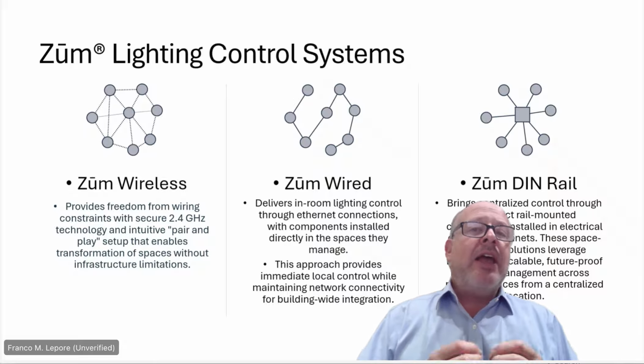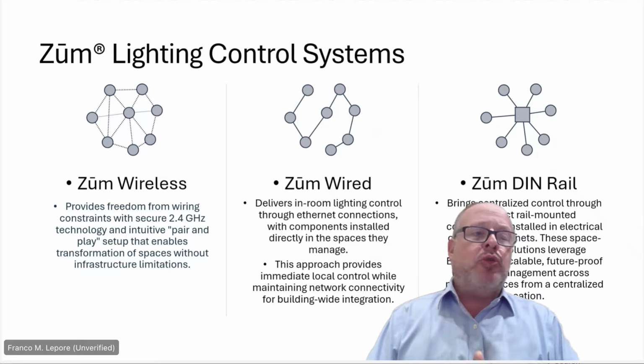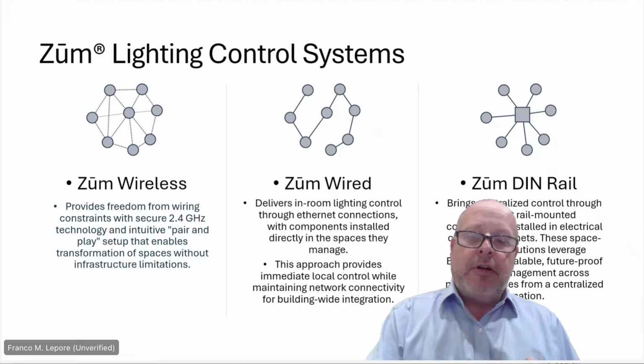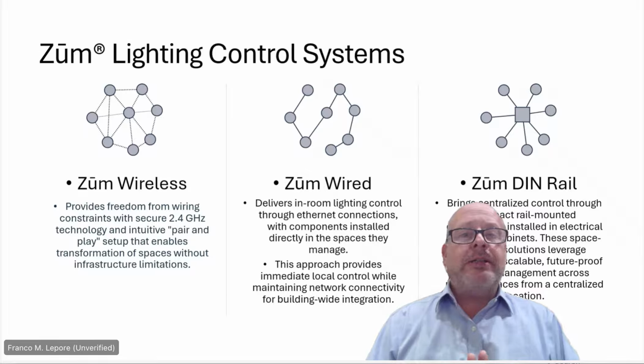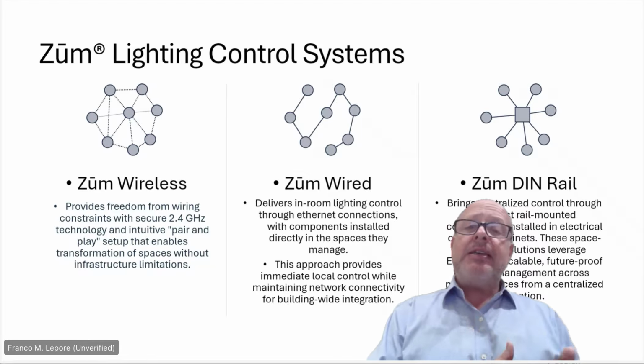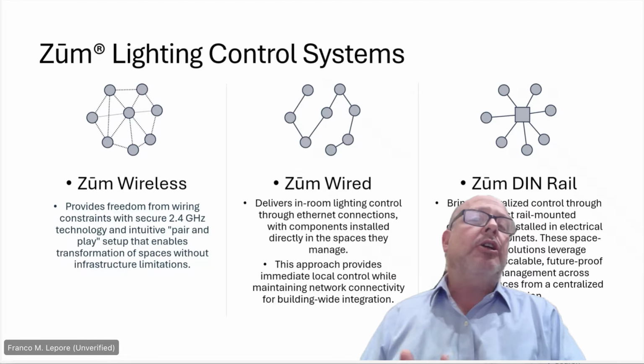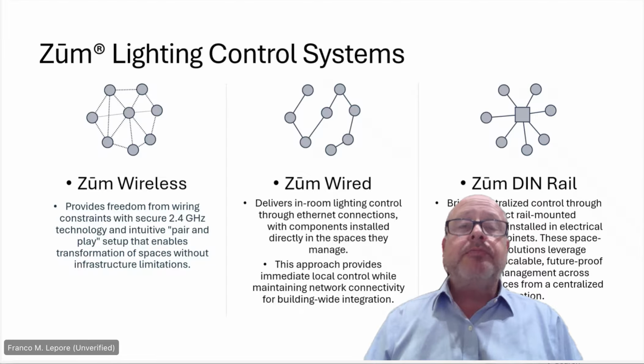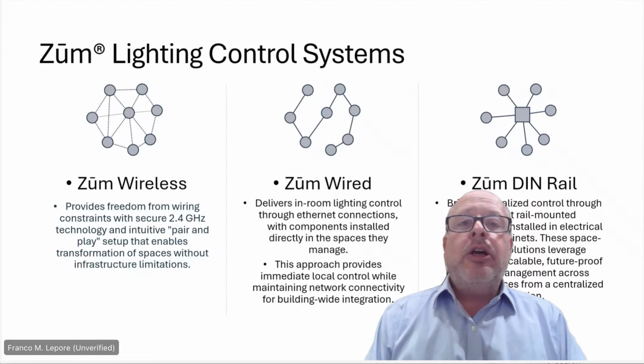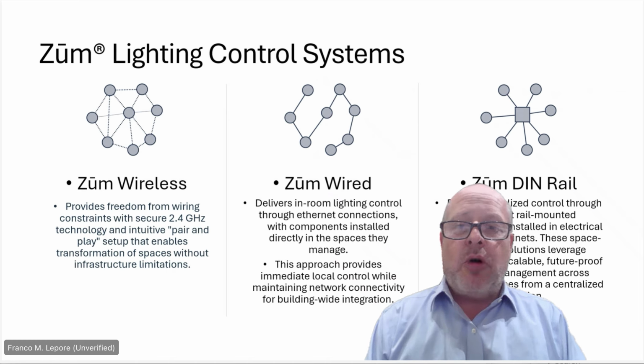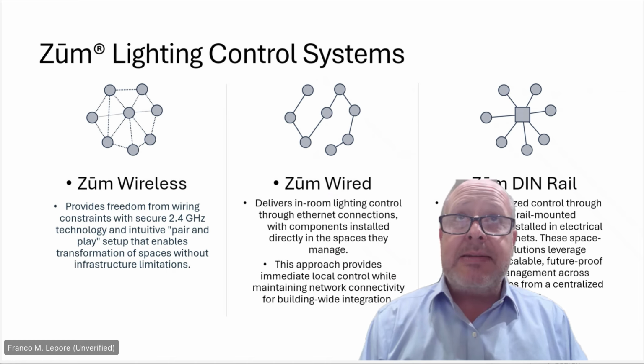What's great about this system is that when these products come out of the box and the electrical contractor installs them, every component knows its duty in life. If a plug load control is added, it knows to act as a plug load control. If it's a phase control device, it knows to control 2-wire phase dimming. You can have up to 32 overall devices in any given space.